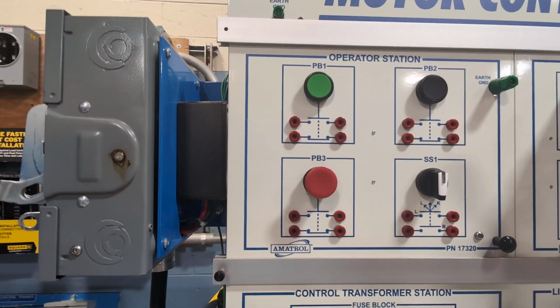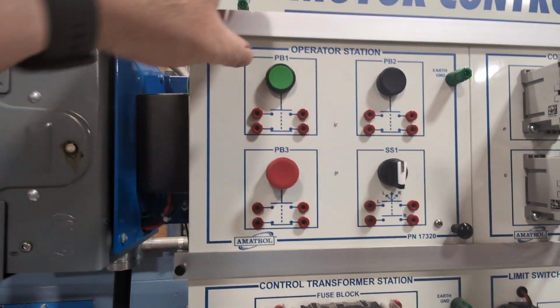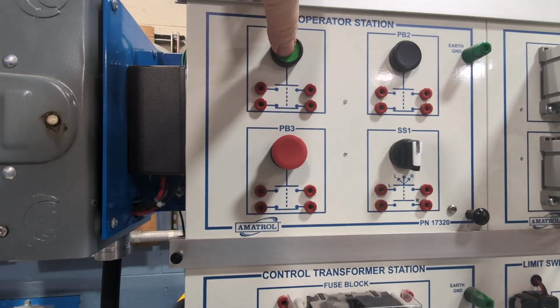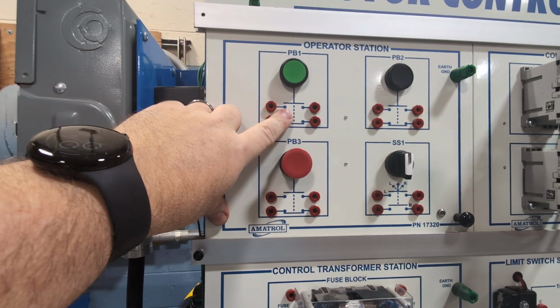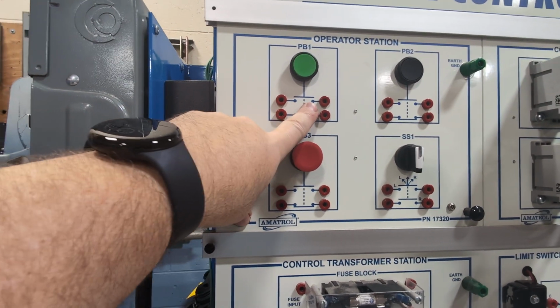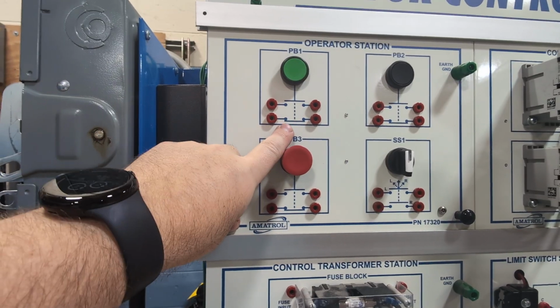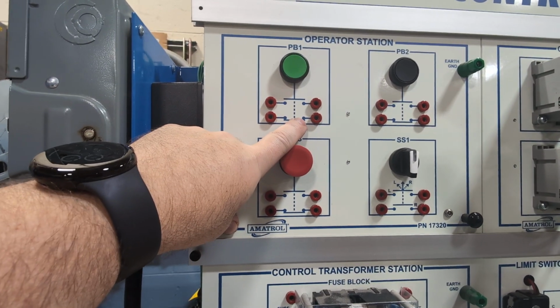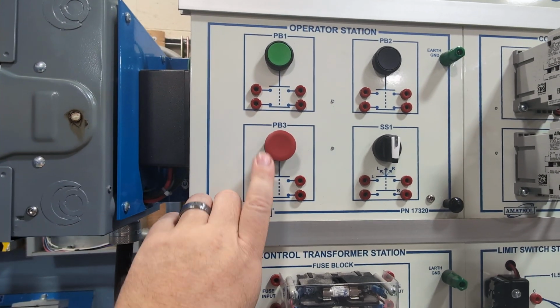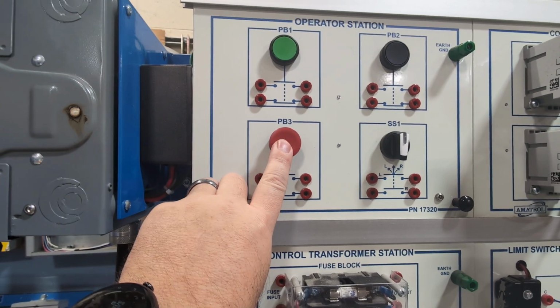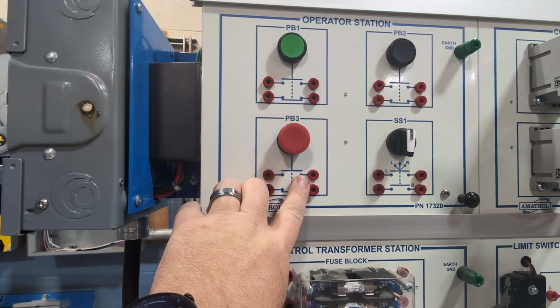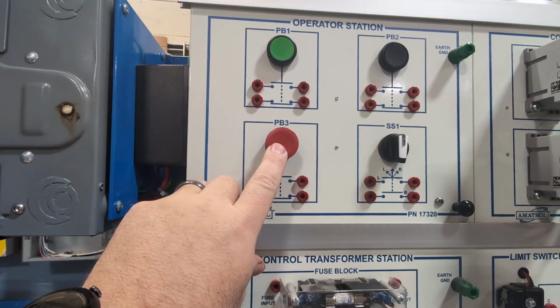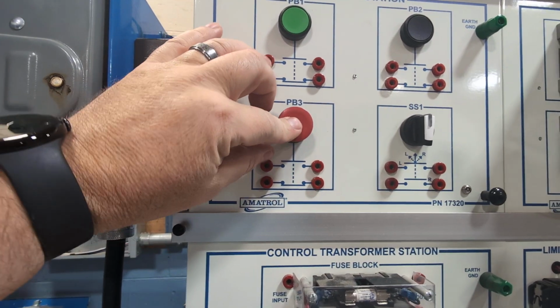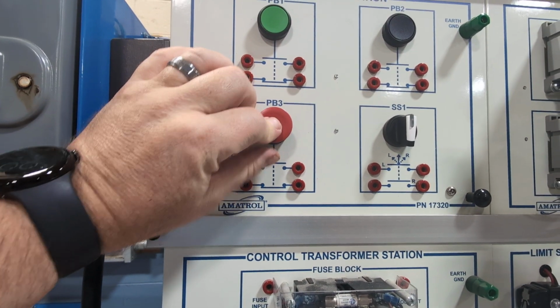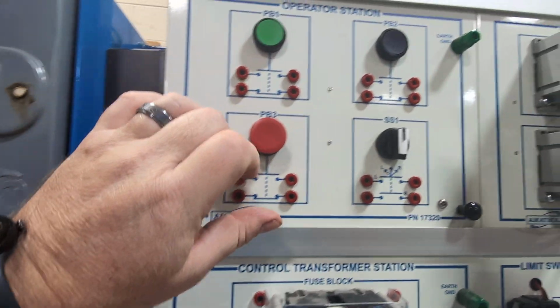This is a motor controller start station. You have your green button to indicate start. You have two contacts. This one right here, not touching, is called normally open. This one here is called normally closed. There's a red button. It's supposed to indicate a stop button. Same deal, normally open, normally closed. When I push this, it changes the state from open to closed, closed to open.